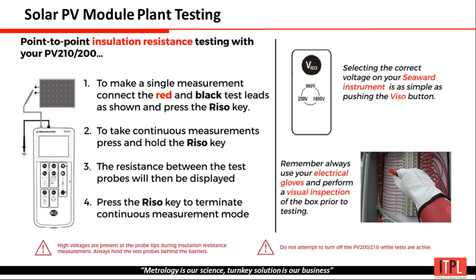How can we conduct the plant testing? Combiner box testing. In every power plant, as we can see, a combiner box is available. So we have to safely open the combiner box, and if you want to test directly at the string monitoring level, we need to open the fuses, connect the crocodile connectors, and make the measurement.